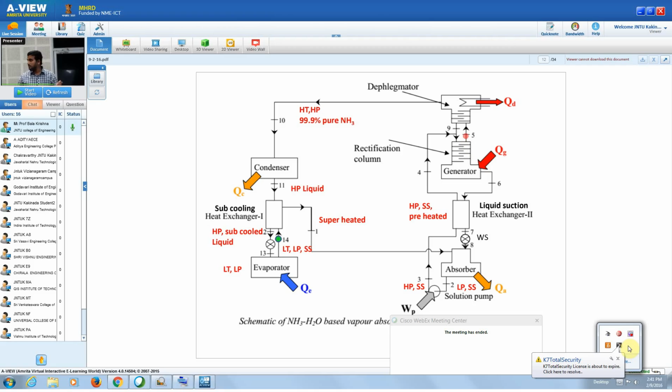the fluid gets vaporized. While getting vaporized, both ammonia vapor and water vapor are evolved. The fluid coming into the generator comes from the top and falls to the bottom of the generator, and because we are giving heat, the fluid already present in the generator gets heated and is converted into vapor, and the vapor moves in the upward direction. Both these fluids move in counterflow, because one moves from the top and the other from the bottom, and there will be both heat transfer as well as mass transfer. Therefore, the solution moving in the upward direction is a vapor.